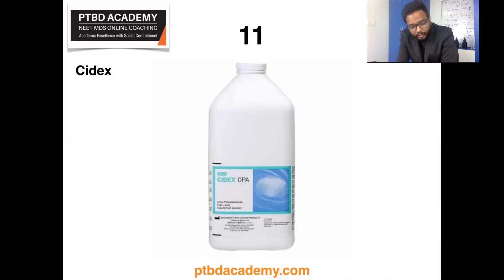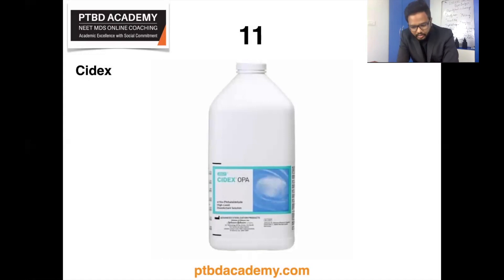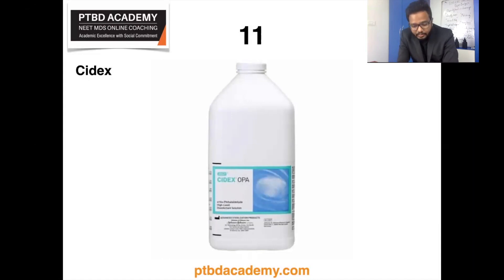Cidex 14-day use — a 2.4% alkaline glutaraldehyde solution — destroys almost 99.8% of Mycobacterium tuberculosis in 45 minutes at 25 degrees Celsius.